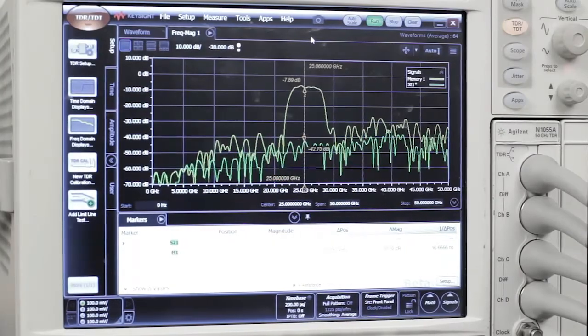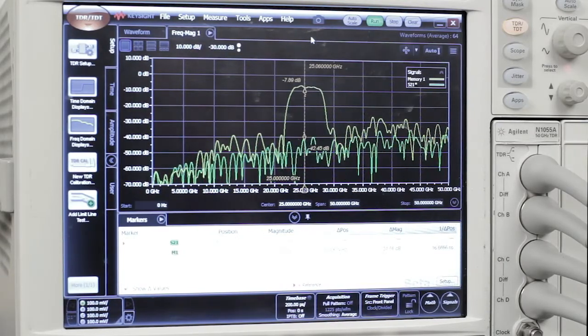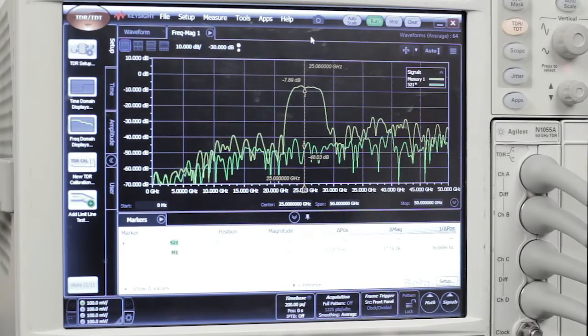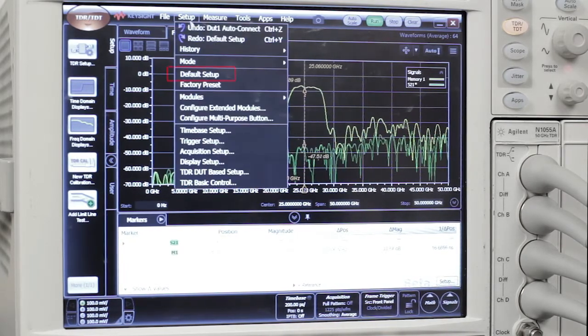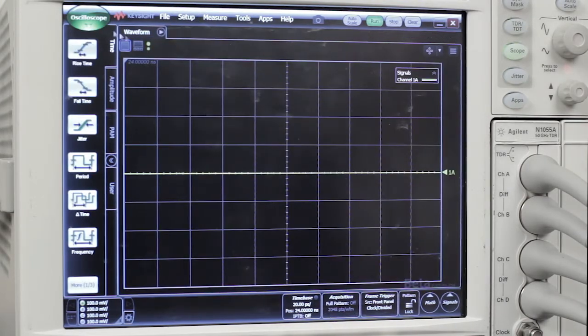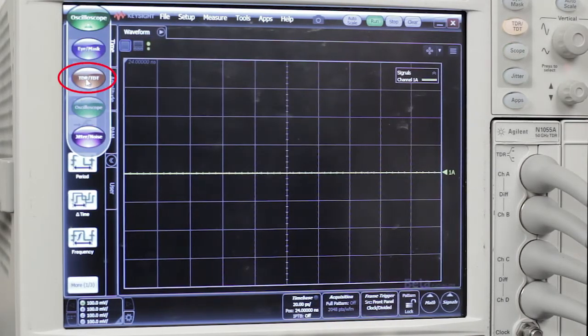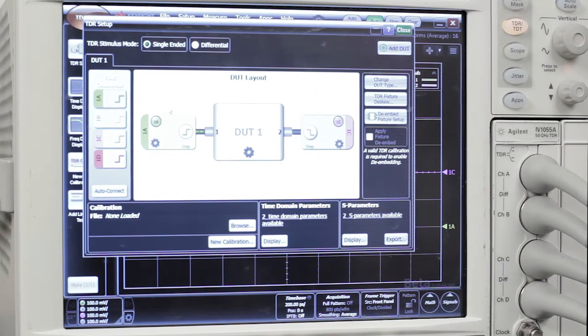The first step in our process today is to set up the TDR for a two-port measurement and then perform a TDR calibration at the reference plane, which is the connector on the remote head. So the best way to start is just with an instrument default setup. Next we'll go into TDR mode and we will choose a two-port DUT since that's what our device is that we're going to measure today.